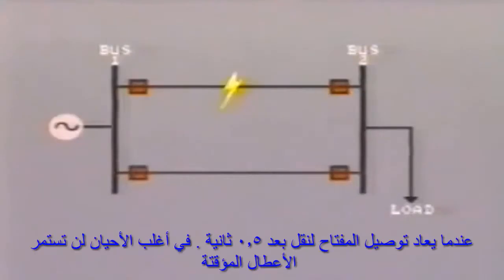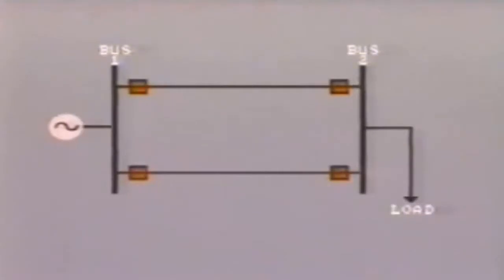One way around this problem is to bring the line back into service again as quickly as possible by automatic reclosing of the breakers. This action is based on the fact that most faults on overhead lines are temporary faults caused by a lightning strike or high winds or other climatic conditions. When the breakers are reclosed after, say, half a second, in most cases, the temporary fault will no longer exist.